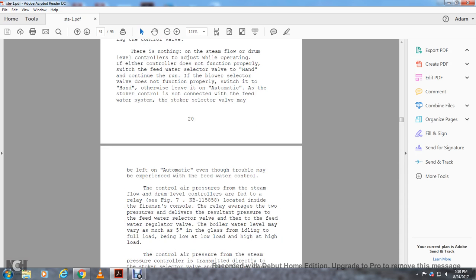The control air pressure from the steam flow and the drum level controllers are fed to the relay of figure 7, the KB-115050, located inside of the fireman's console. The relay averages the two pressures and delivers the resultant pressure to the feed water selector valve and the feed water regulator valve. The boiler water level may vary as much as 5 inches on the glass from idling to full load, being low at low load and high at high load.